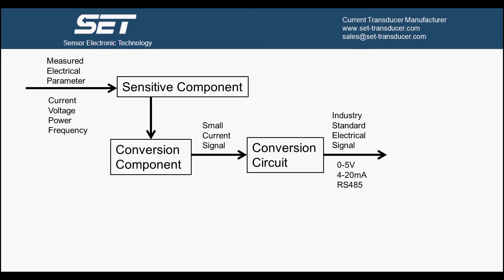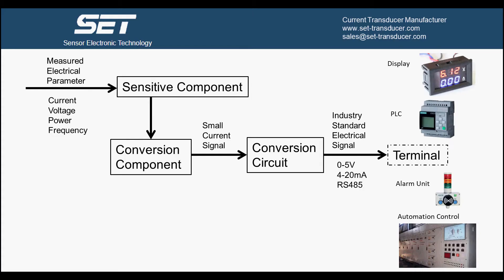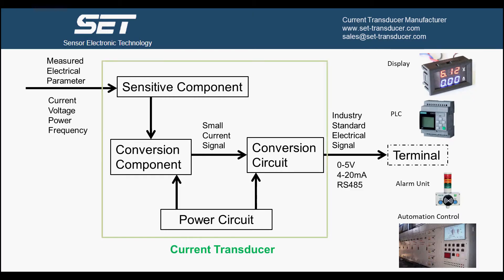The output is usually at 0 to 5 volts, 4 to 20 milliampere, or RS485. At the end, the output signal goes to terminal equipment such as display, PLC, alarm unit, automation control, etc. Current transducer usually has a power circuit, which provides power to the conversion component and conversion circuit.